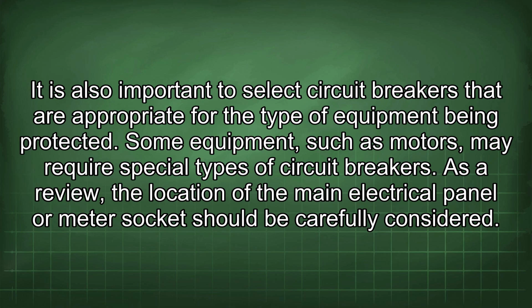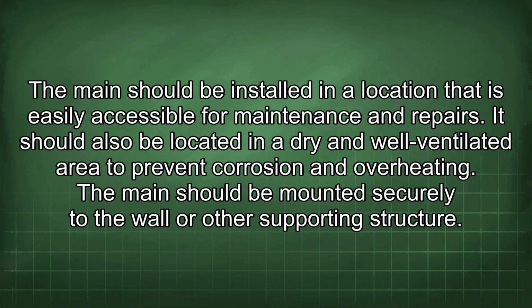Some equipment, such as motors, may require special types of circuit breakers. As a review, the location of the main electrical panel or meter socket should be carefully considered. The main should be installed in a location that is easily accessible for maintenance and repairs. It should also be located in a dry and well-ventilated area to prevent corrosion and overheating.